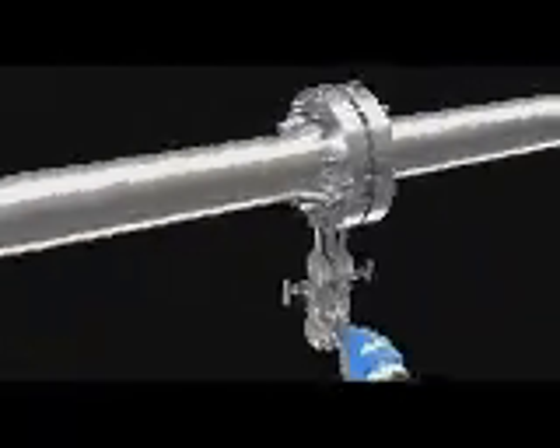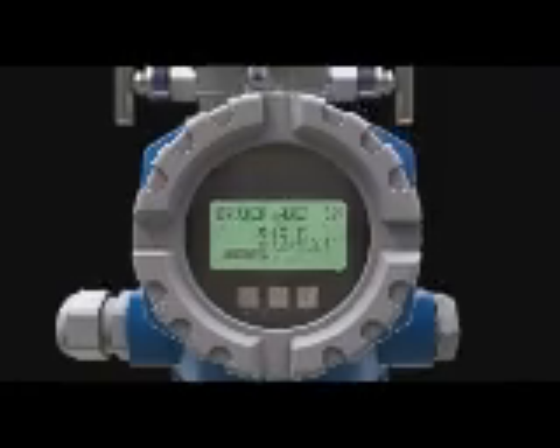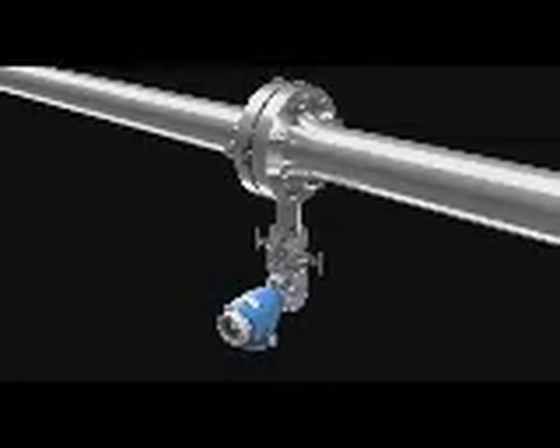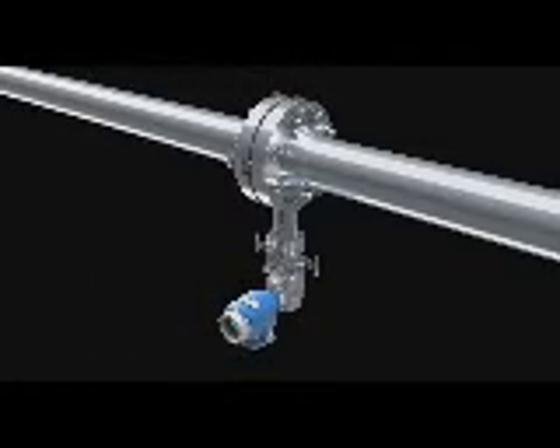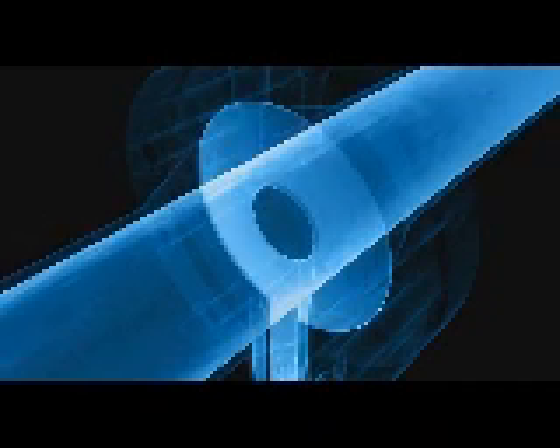One method is flow measurement, based on the differential pressure principle, known as the Venturi tube. Here is how this measurement method works. Differential pressure flow meters have an artificial restriction integrated into the measuring tube, illustrated here by the example of an orifice plate. Two holes are located in the pipe wall, one before and one after the orifice plate.